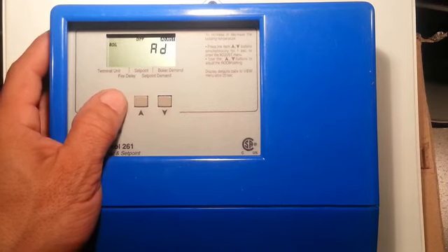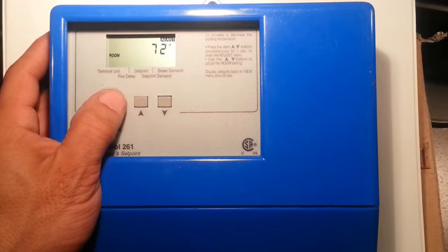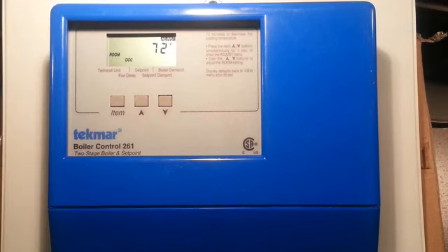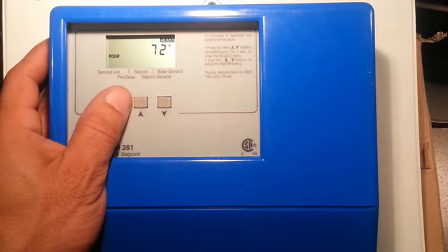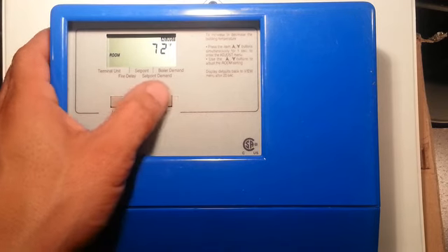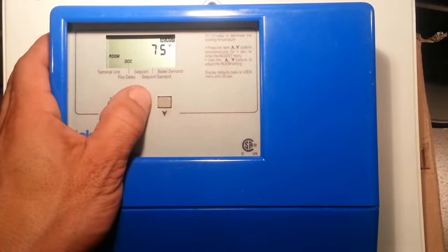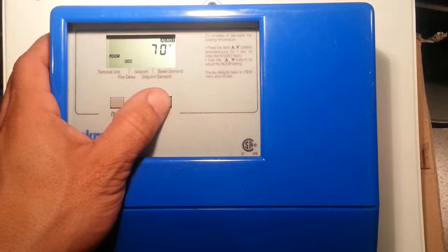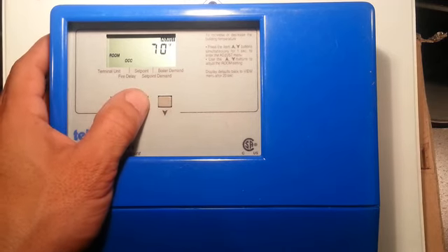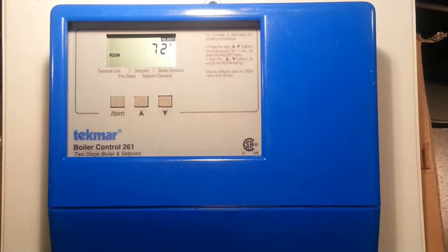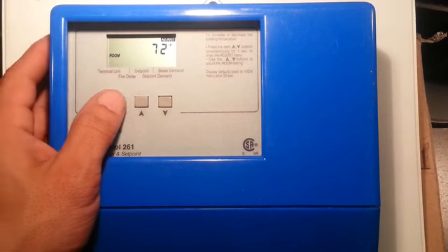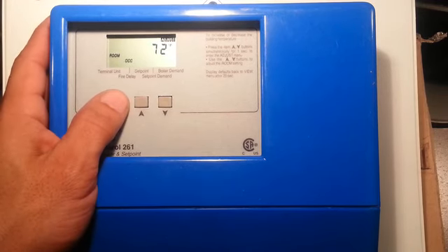If we go back to that room OCC setting, this is the setting that you would tell your customer about if you wanted to give them some ability to adjust or tweak the temperature. You would say just go to room occupied, set this temperature up or down depending on whether you wanted the room hotter or colder, set it below the 72 degrees. And this is what it does in the internal control: it does a parallel shift of the heating curve that you're going to set in the further adjustments down the line here.